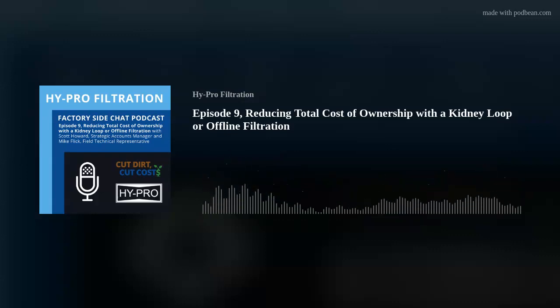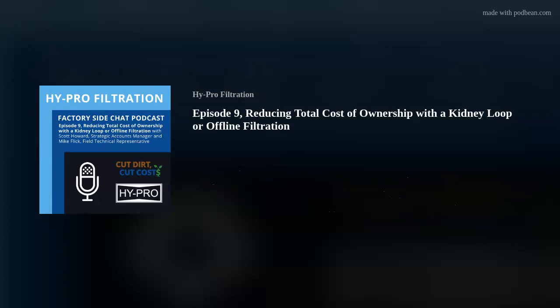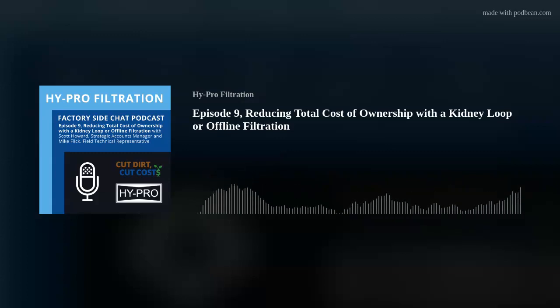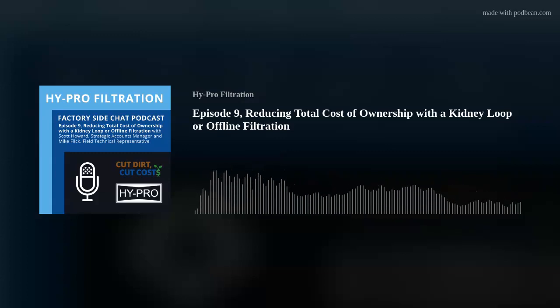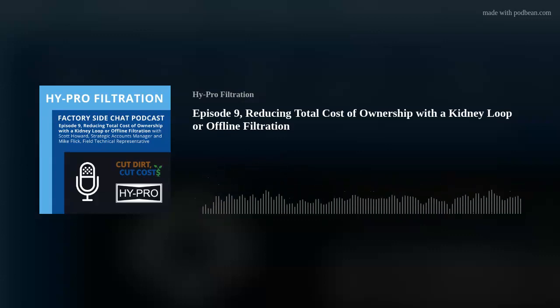A few other areas that I'd like to hit on as far as benefits of a kidney loop or offline filter unit: as we size it properly, as you'd mentioned, we then intentionally have the tightest filter element in the kidney loop for the system, whether it's a 3 micron or 1 micron or even submicron based on the application. So the kidney loop does the lion's share of the work in the system. I look at it as the polishing filter element that does the heavy lifting, which allows the inline filters to focus on internally generated contamination in the line. And so they last longer.